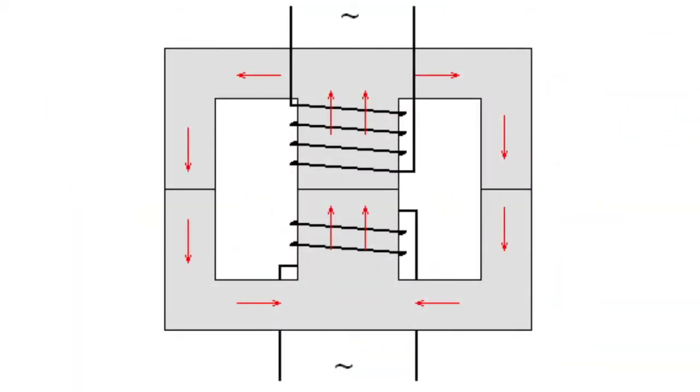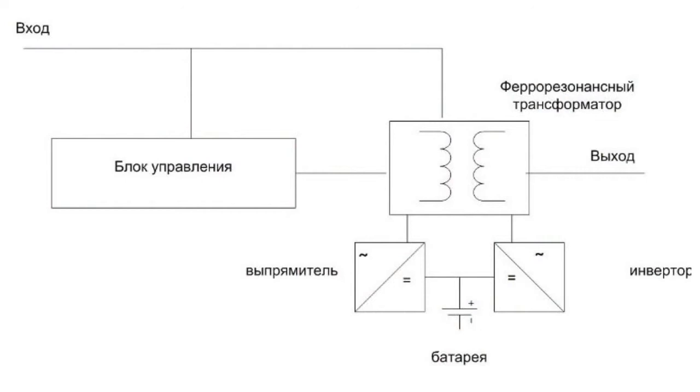A ferroresonant transformer has a considerable inductance. A great amount of energy accumulates in the transformer's magnetic field during the UPS operation from the main. When power supply stops, the transformer supplies the energy which has been accumulated in its magnetic system into the load during 8-16 milliseconds.